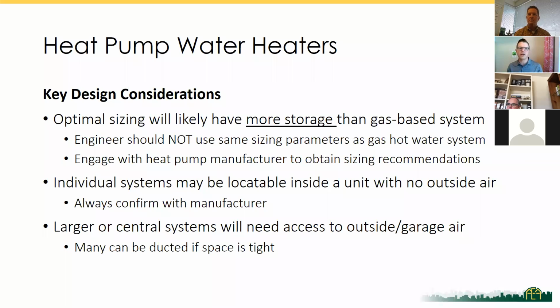Some key design considerations for heat pump water heating: if you take one thing away from this presentation, it's that optimal sizing for a heat pump water heater is likely to require more storage than a gas-based system. With gas water heating, we've been moving to less and less storage, the ultimate endpoint being tankless water heating. Tankless gas water heating is very efficient because gas power is cheap, so you just put a big blowtorch on your incoming water and heat it with a ton of gas all at once, and that works fine.